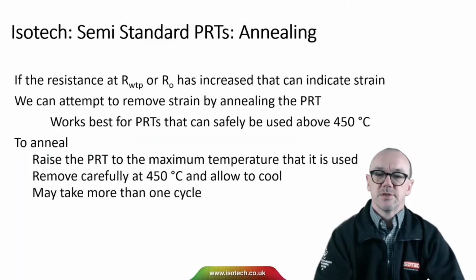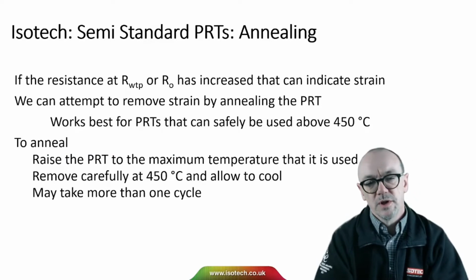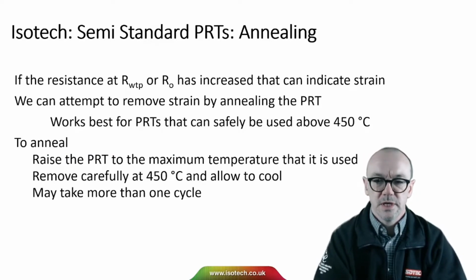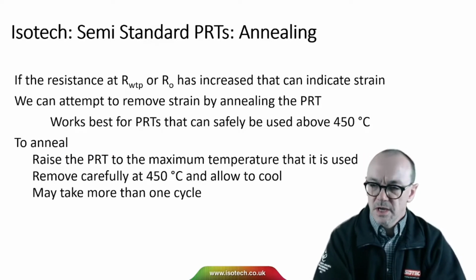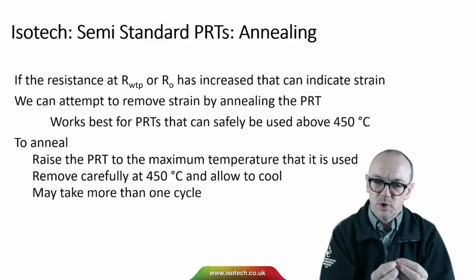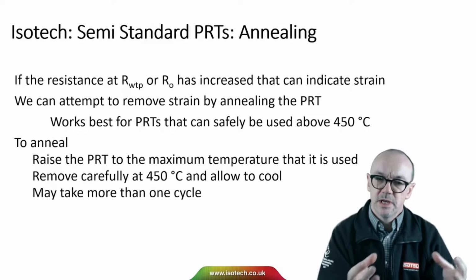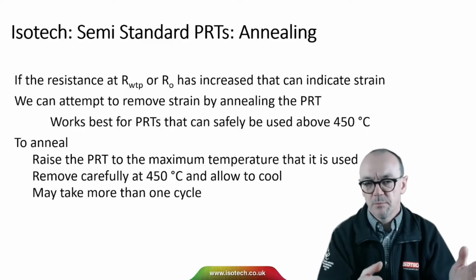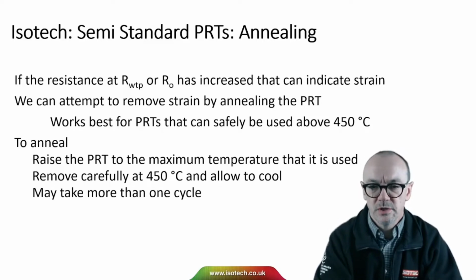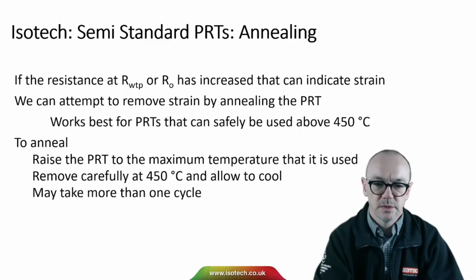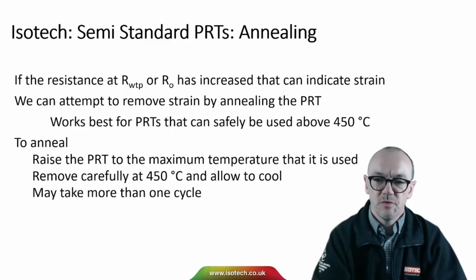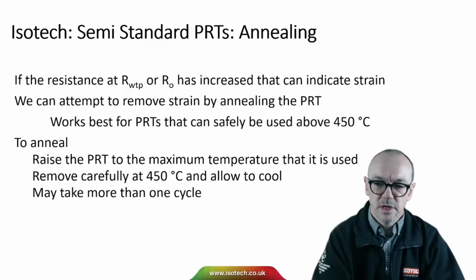If the resistance at the water triple point, or the resistance at 0 degrees C, has increased, that can indicate strain. So if the wire inside the thermometer becomes strained, we'll see an increase in resistance, and we can see that by making measurements at the water triple point or perhaps the ice point. And we can attempt to remove that strain by annealing the PRT. It works best for PRTs that can be safely used above 450 degrees C.